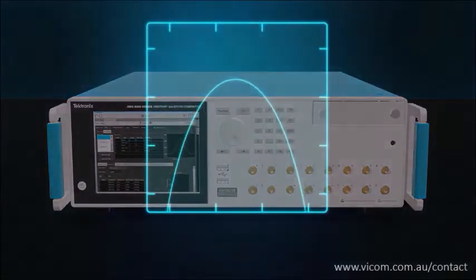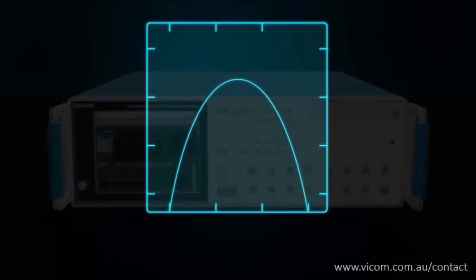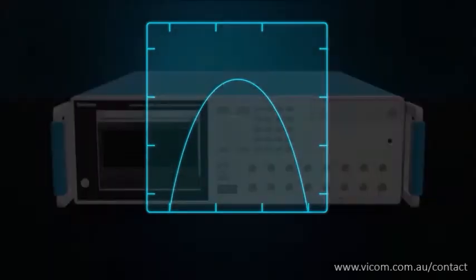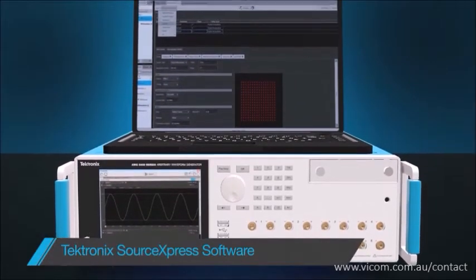Powerful digital upconversion technology incorporates a digitally implemented mixer and a local oscillator into the output, allowing for fluid, seamless center frequency adjustments. It's driven with Tektronix's powerful SourceXpress software.